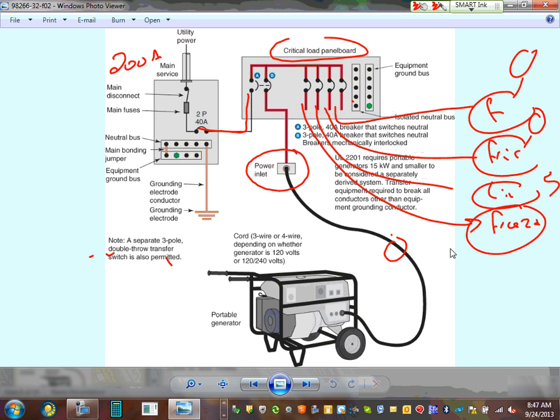If you're holding it in your hand, you're not looking, you can't touch anything. So you bring your cable and the three hots, and these three hots are inside and you plug them in the switch. The reason why they do it this way, guys: the male part is here, and the female part is here with the cable. Because you don't want to imagine running your generator, and you're looking at hot and neutral right here in your hand, like the end of a switch, the male part of a switch. It's for safety.